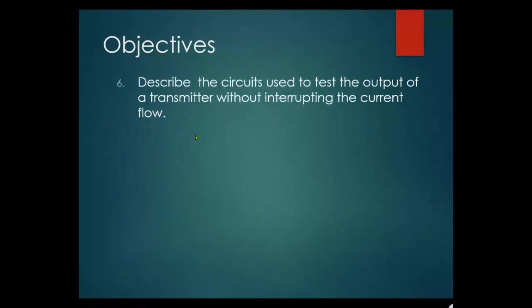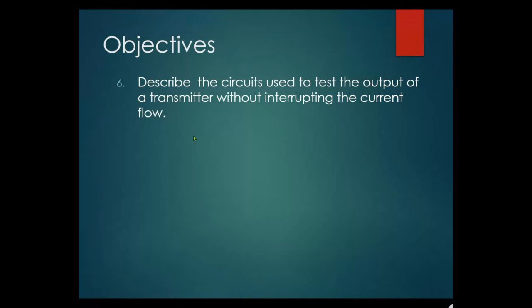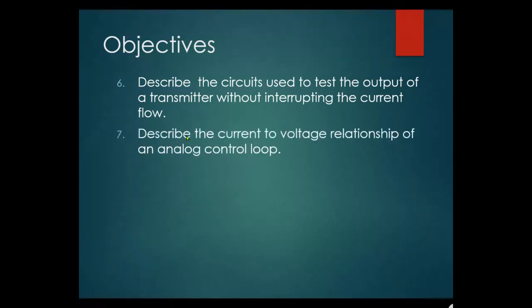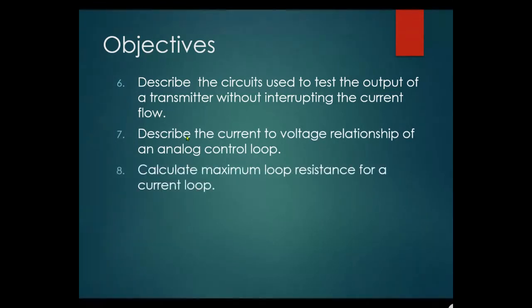Objective six: describe the circuits used to test the output of the transmitter without interrupting current flow. When we go across the test leads on a transmitter, there is a silicon diode, and the voltage drop across it is 0.7 volts. If you open the loop to measure current, you'll shut down the loop. With test leads, it's essentially a forward-biased diode allowing current to flow, so we can test current without opening the loop — the loop stays running.